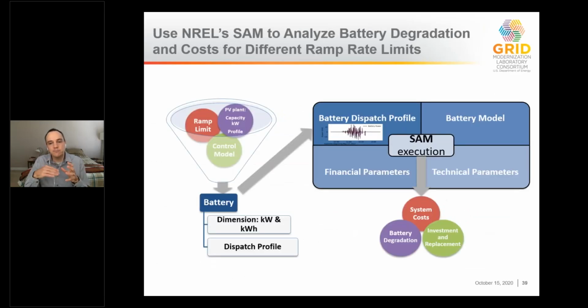So we took that battery dispatch profile and the characteristics of that battery in terms of the dimensioning of it, and ran an analysis where we would look at different ramp limits, and use this on different PV profiles. We put that into NREL's SAM model, which has the ability to reflect some of the battery operations and some of the degradation that might occur as you start to cycle batteries. And then we used that to calculate what the total system costs would be, how often that battery would be degraded and then need to be replaced, and so on. And really that replacement comes from that cycling of the battery, that it can be costly to cycle that battery very quickly. And again, in this case, we're talking about something like a lithium ion battery providing this service.